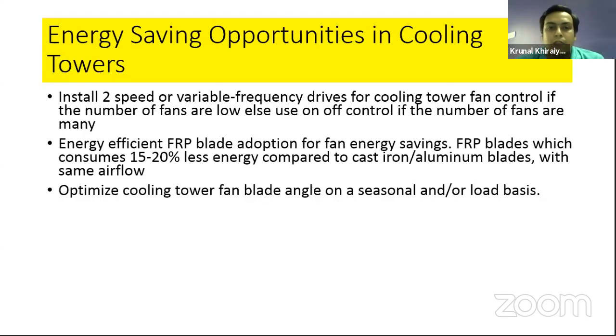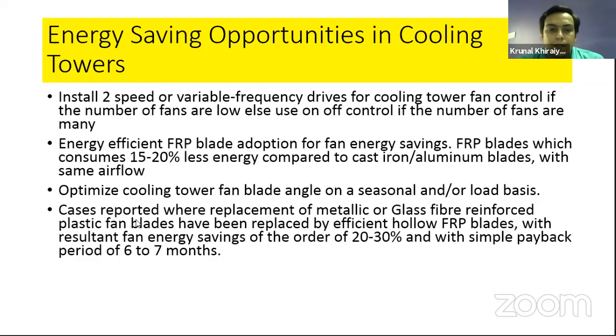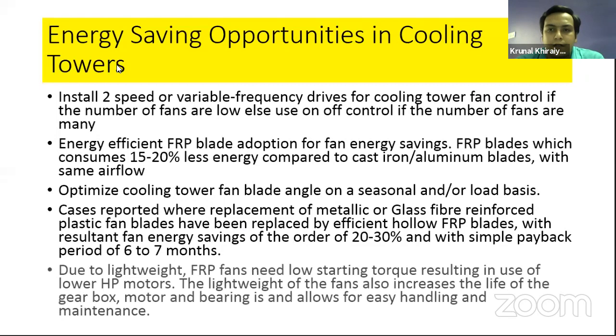So based on that, you can save some amount of energy. Yes, cases are reported where metallic or glass fiber reinforced plastic, that is FRP, fan blades have been replaced, and FRP blades give savings in the range of 20 to 30%. If you go for the replacement of these types of fans, the simple payback period is about 6 to 7 months. Meaning if you are replacing the old fan with a new fan with FRP blades, then definitely your simple payback period is near 6 to 7 months. So go with all the opportunities available for our fan.